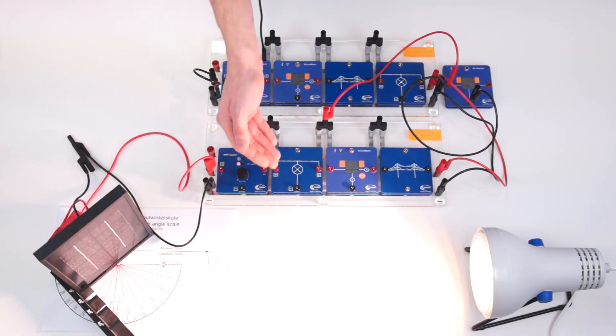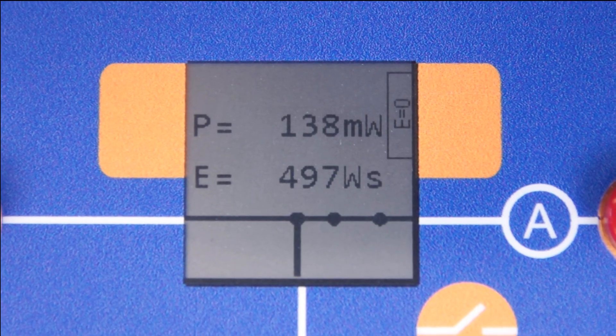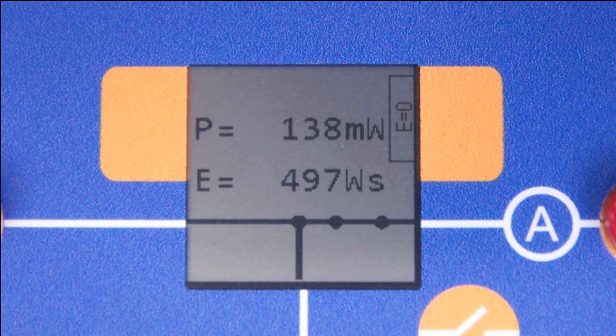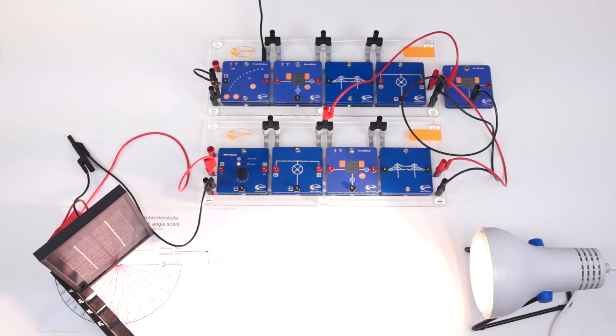This means that the second household is completely supplied and the first household is partially supplied by the photovoltaic system. In contrast, the power of the transformer is decreased. Here, a value of 138 milliwatts can be read. In reality, this means that the adjoining medium voltage grid releases less energy in the strand due to the higher photovoltaic power.